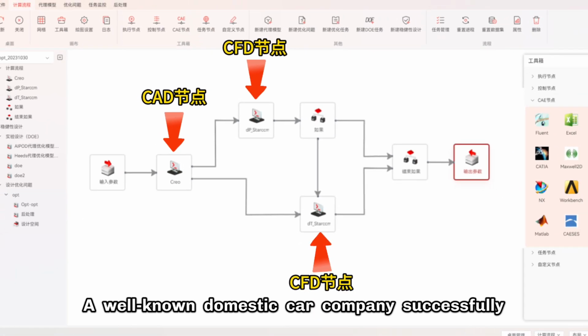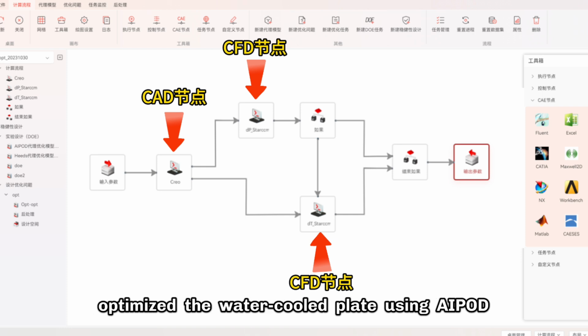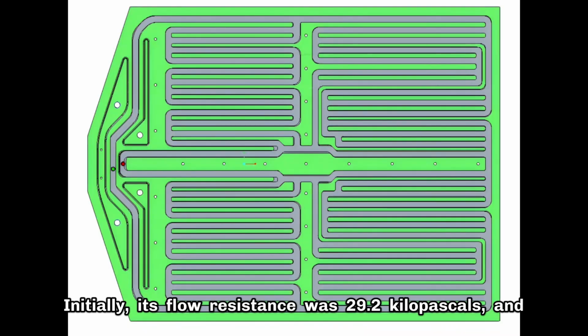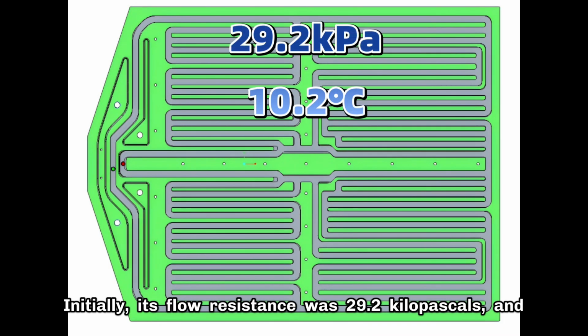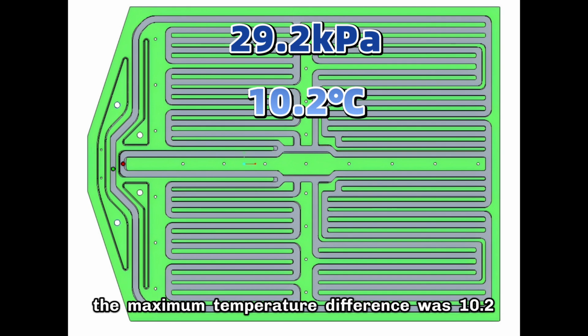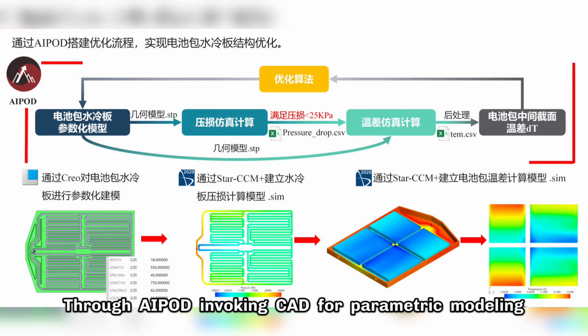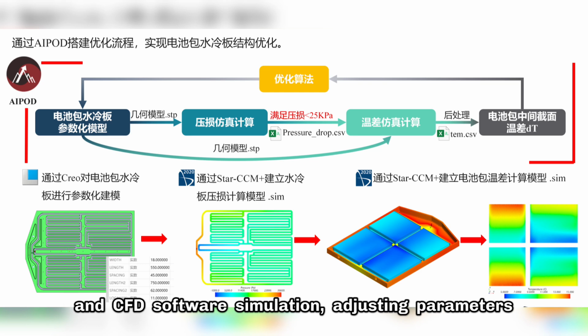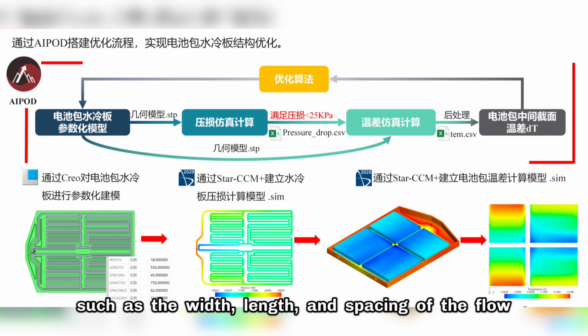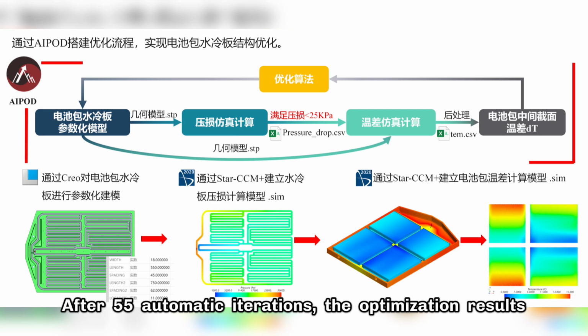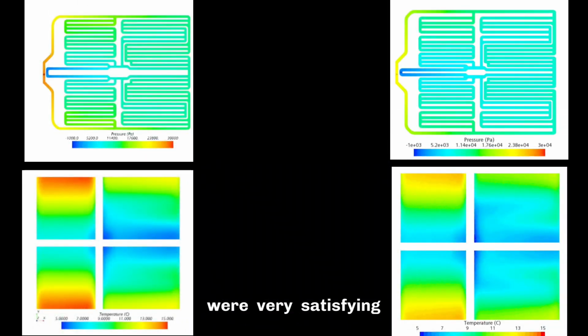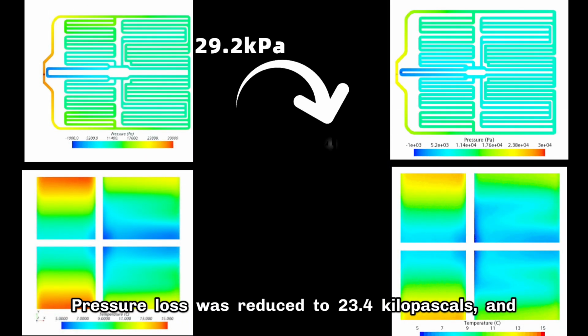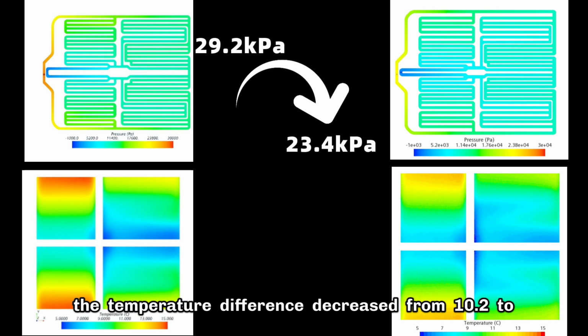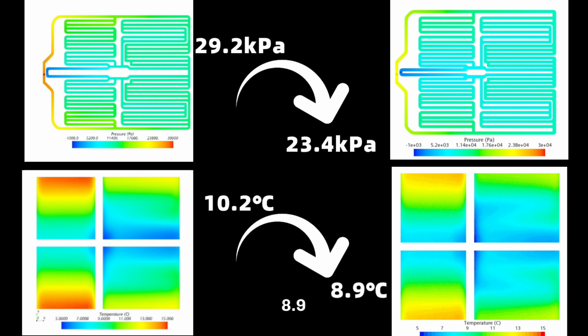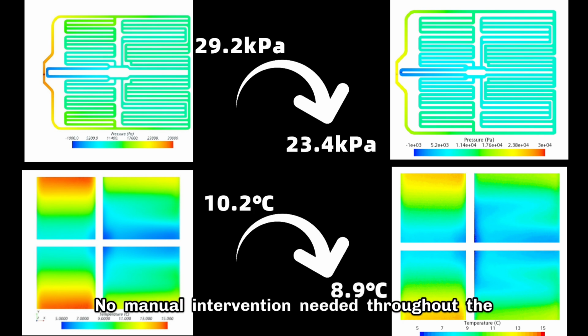A well-known domestic car company successfully optimized the water-cooled plate using AIPod. Initially, its flow resistance was 29.2 kilopascals, and the maximum temperature difference was 10.2 degrees. Through AIPod invoking CAD for parametric modeling and CFD software simulation, adjusting parameters such as the width, length, and spacing of the flow channels, after 55 automatic iterations, the results were very satisfying: pressure loss was reduced to 23.4 kilopascals, and the temperature difference decreased from 10.2 to 8.9, with no manual intervention needed throughout the process.